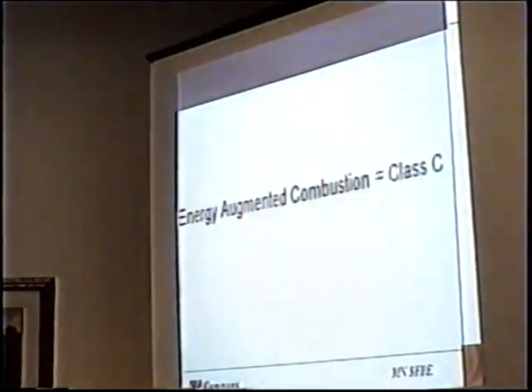So energy augmented combustion, and the reason why I talk about that is because some people equate it to Class C, but we never really had a good definition of what Class C is. Something that involves electrical energy. But energy augmented combustion can be a number of different things, not just electrical in nature. You can have radiative energy that's added to it, that will affect the fire. You may have conductive energy that's in there, arcing and so forth. So really, we haven't had a real good definition of what Class C is. And as a result of that, we really want to go away from that Class C definition and talk more in terms of energy augmented combustion.